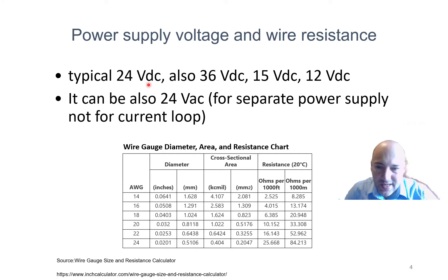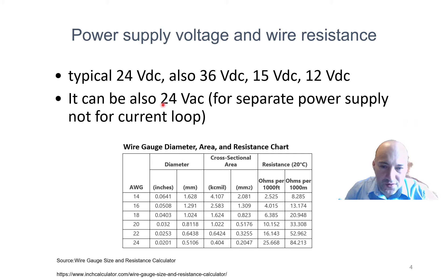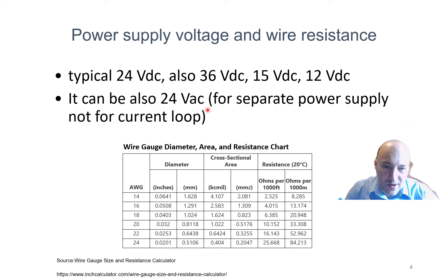If you are using AC voltage, you cannot power the sensor directly from the current loop — this only works for DC voltage. Using AC will give you at least a three-wire connection between your sensor and your controller system.